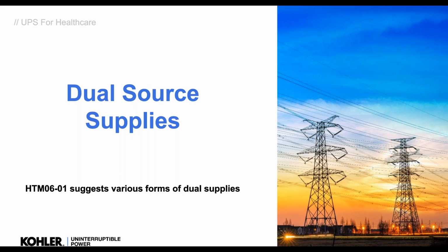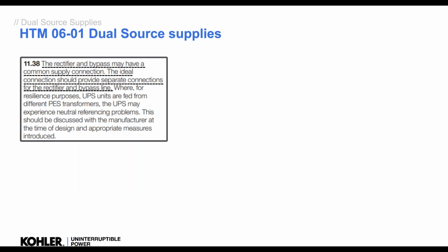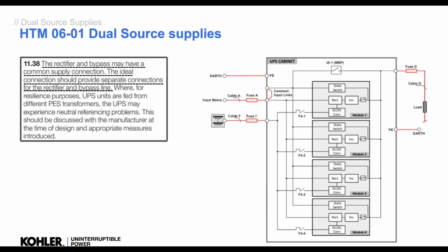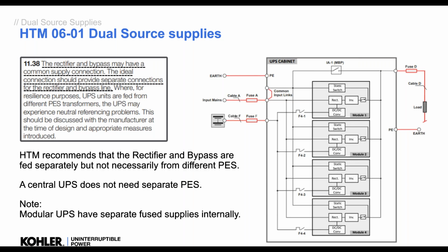What we do find a lot of questions around is dual supplies and the requirements of HTM 0601. It suggests that the rectifier and bypass may have a common supply connection. The ideal connection should provide separate connections for the rectifier and bypass line. So when we look at a UPS, we typically have a supply, and if it's a single source, we link out the rectifier and the bypass, so we have a single source. If we want it to be dual feed, we take out these links and feed another supply onto the bypass supply. So it doesn't necessarily have to have it. It depends how we're going to do it.